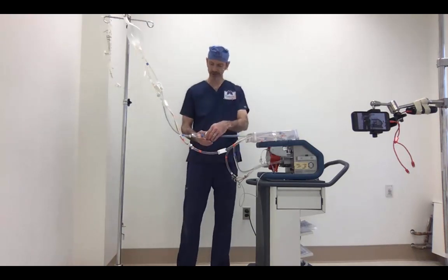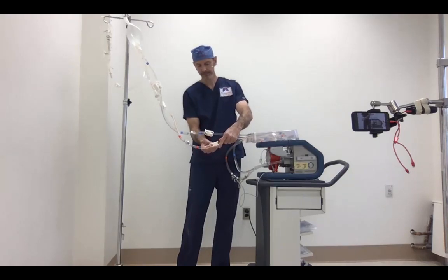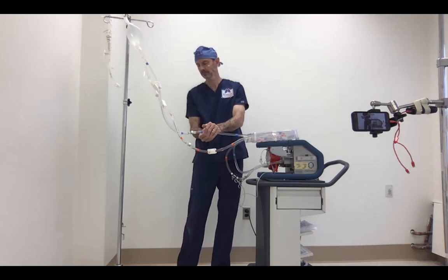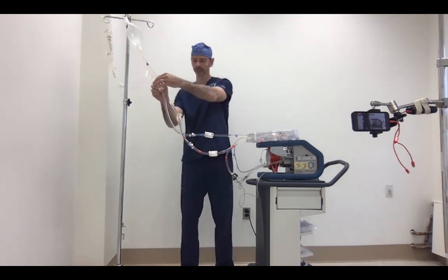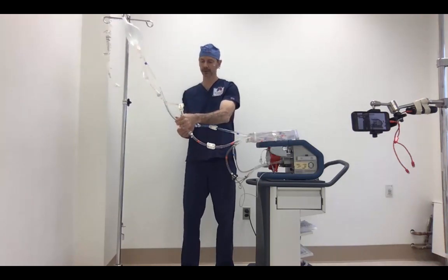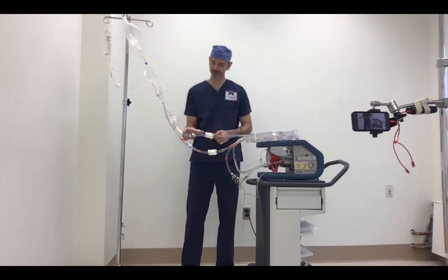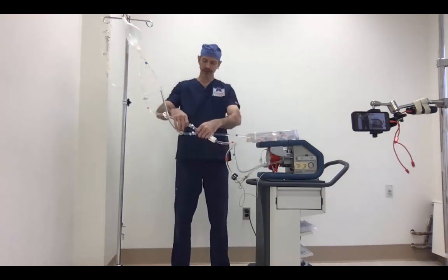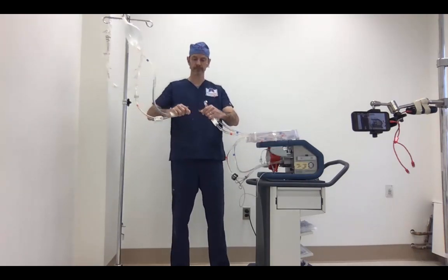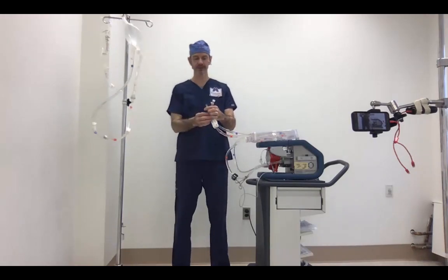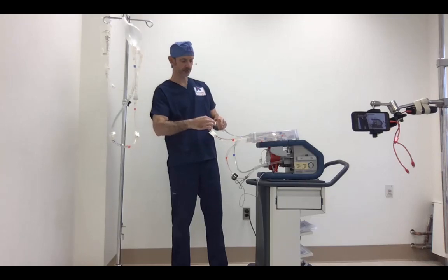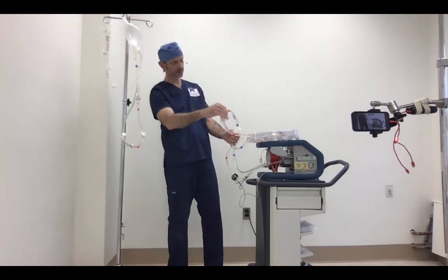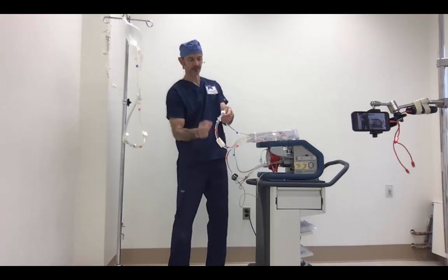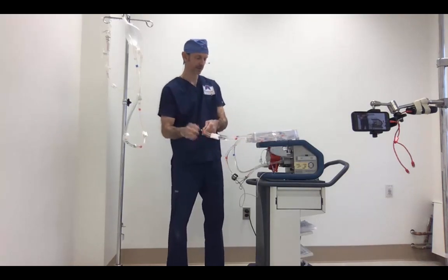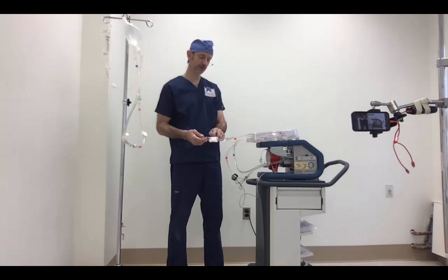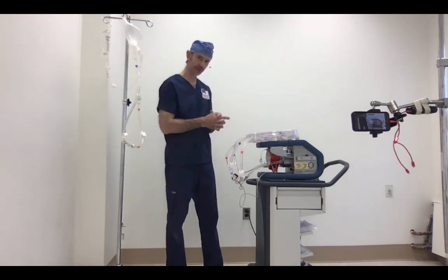I'll do that in just a second, but as long as I'm standing here, let's clamp these lines. I'm moving the thumb clamps closer to the connection because this fluid here is probably going to spill out. Then we can disconnect this. Connect the bag to itself just to keep the sterility and minimize the mess, and put these two together. You see there is a bubble in there, right here, but that's not going to be a problem as long as we keep it between these clamps. So the clamps are closed, the bubble is trapped. This bubble is never going to make it to the surgical field if we are careful with these clamps. Let's zero that flow probe now.